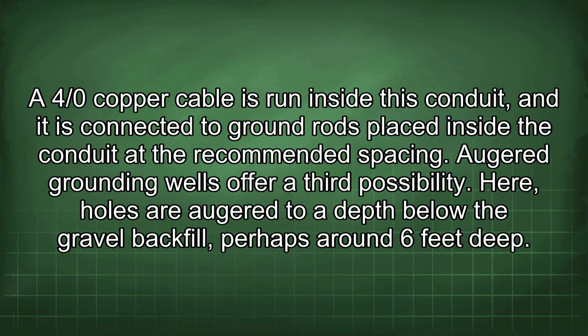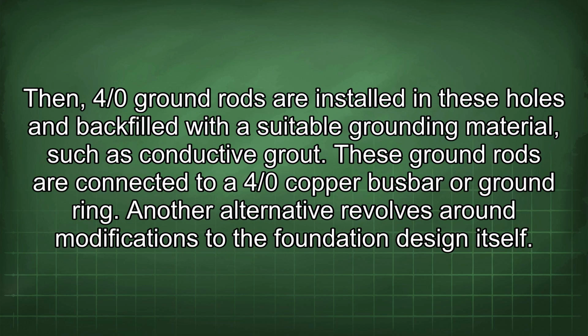Augered grounding wells offer a third possibility. Here, holes are augered to a depth below the gravel backfill, perhaps around 6 feet deep. Then 4/0 ground rods are installed in these holes and backfilled with a suitable grounding material such as conductive grout. These ground rods are connected to a 4/0 copper busbar or ground ring.